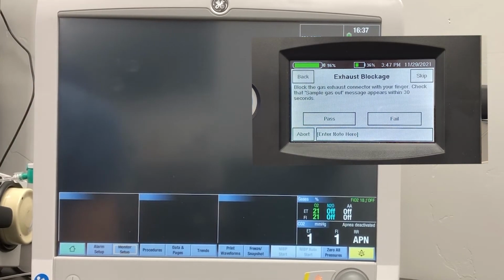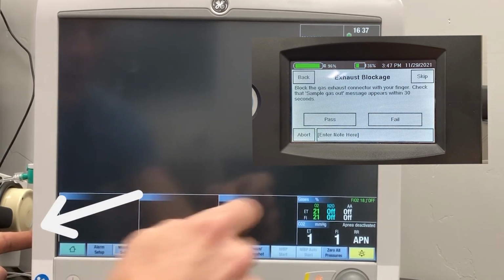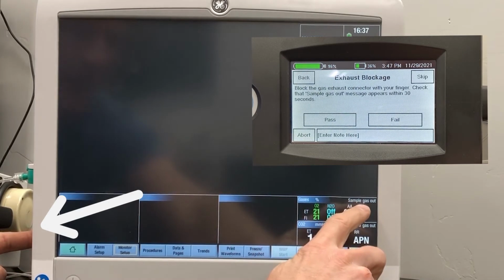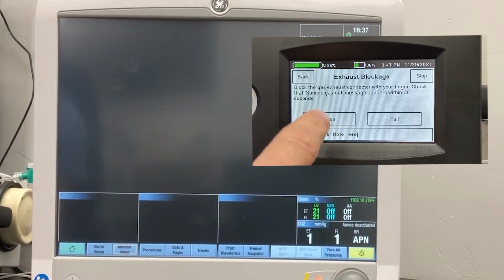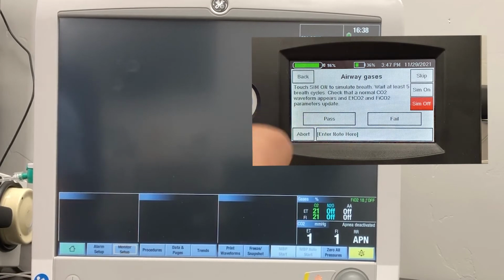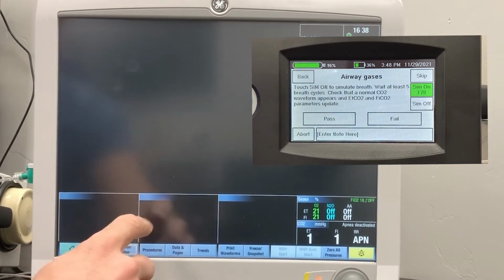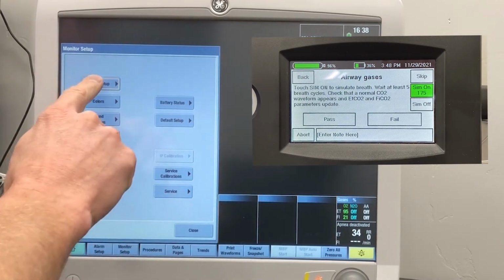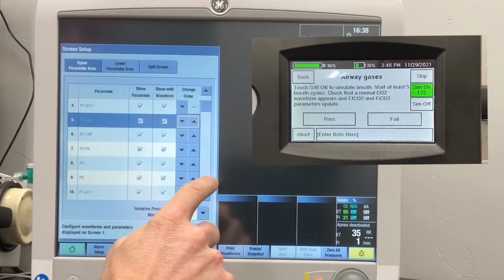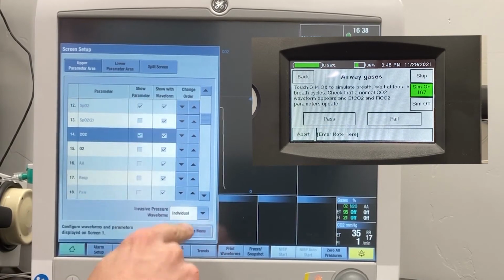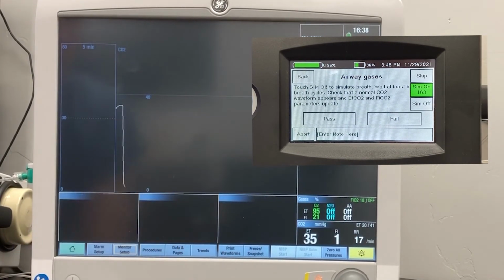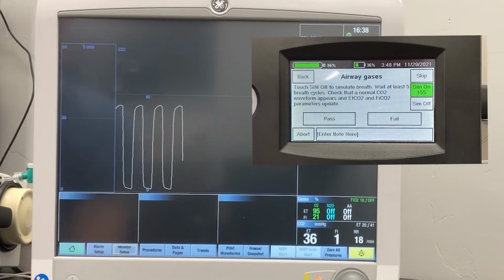Next we're going to block the gas exhaust with our finger. We'll watch over here and make sure that it gives a sample gas out alarm so we can let go. So that's passed. So now we're going to simulate breath. Come over here and set the monitor up, screen setup, scroll down till we see CO2. You can see it's tracing the CO2 waveform there. Here we're just checking that it alternates up and down and looks like a believable capnogram. So that's a pass.